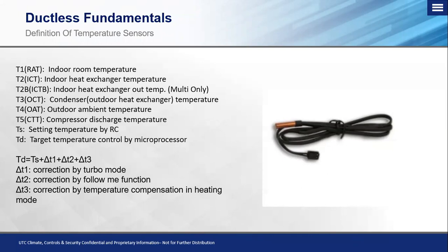So the most important thing that I can tell you about follow me is when a customer wants to do this or they have questions about it, if they are going to use the follow me mode, they need to make sure that that is the only wireless control that they are using for that indoor unit. You cannot control multiple indoor units from one wireless controller when you have the follow me enabled, because it's locked into that particular unit to read the room temperature, report it to the unit so that it can run properly and maintain temperature. Okay. The other biggest thing with follow me is you don't want to put this system in follow me on the wireless remote control and have the customer put the remote where it's not in line of sight of the indoor unit. If they decide to put it in follow me and then put it in their dresser drawer, or one of the kids take it and they end up losing it, it will drop out of the follow me function. And as a default, it will look at the T1 sensor, because the system has to realize what the temperature is in the room in order to be able to control and modulate the rest of the system properly.